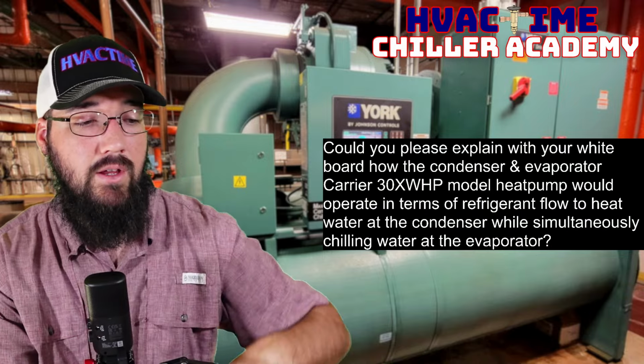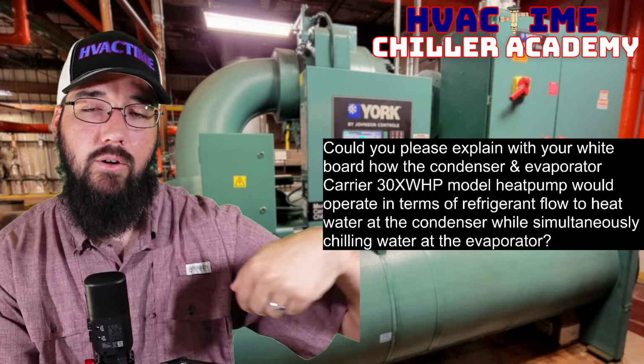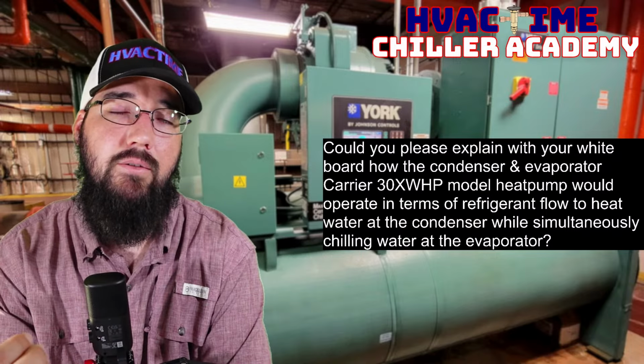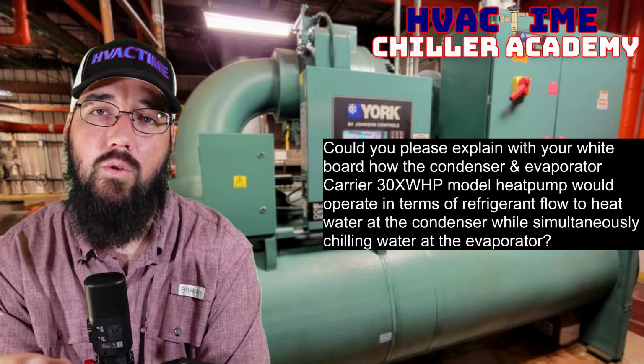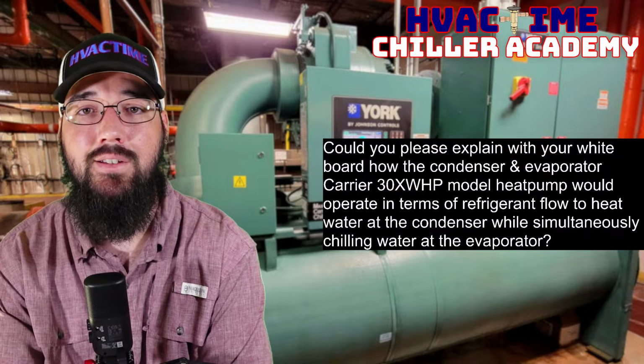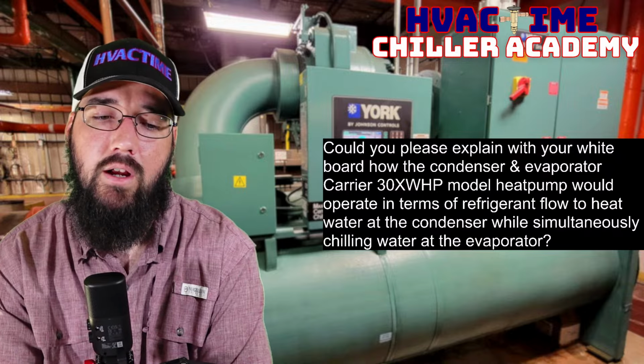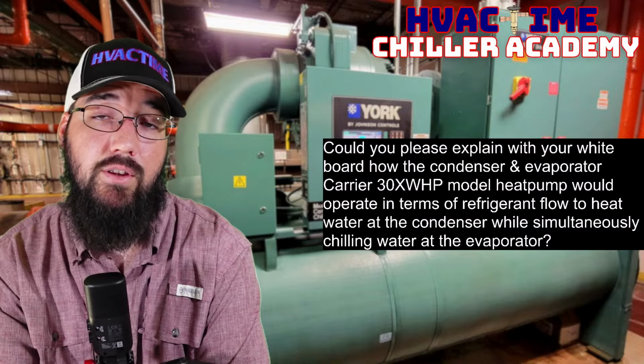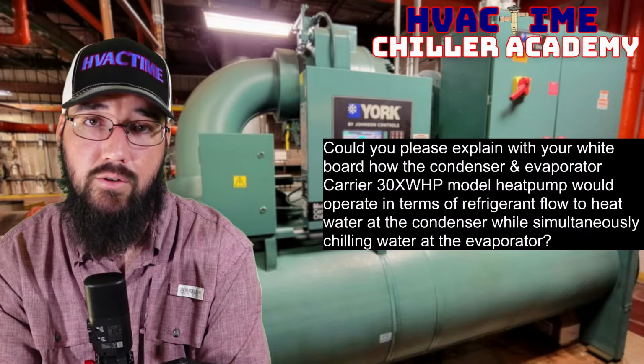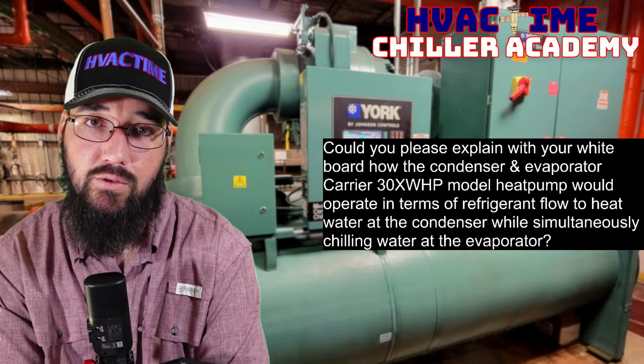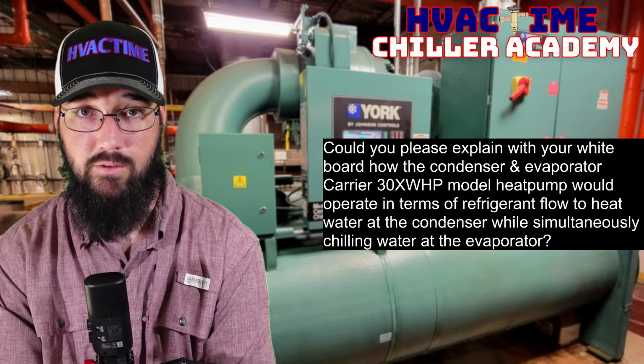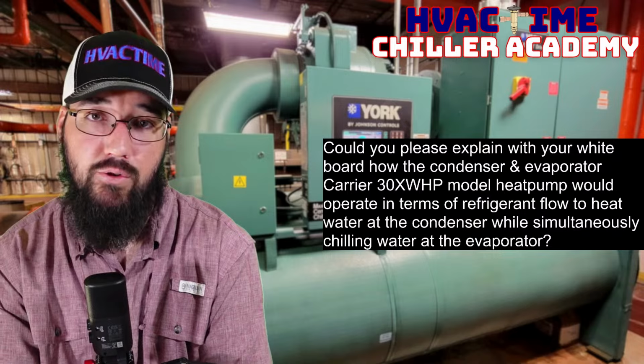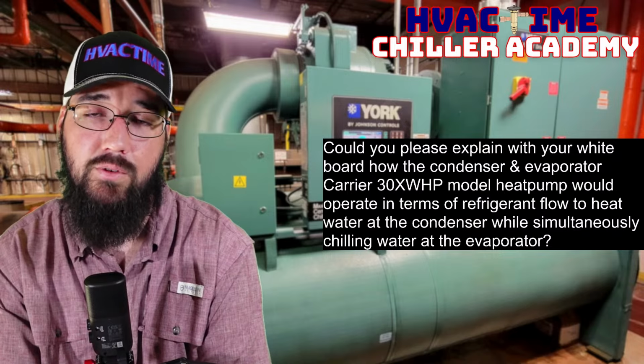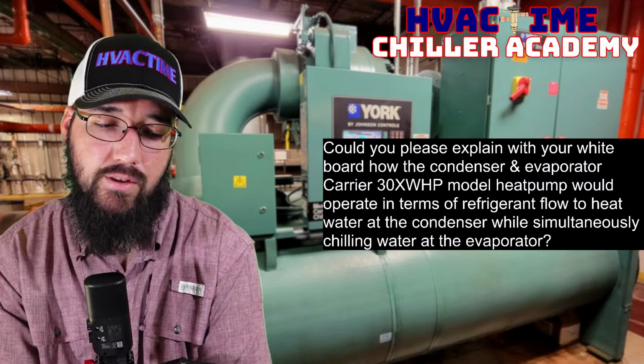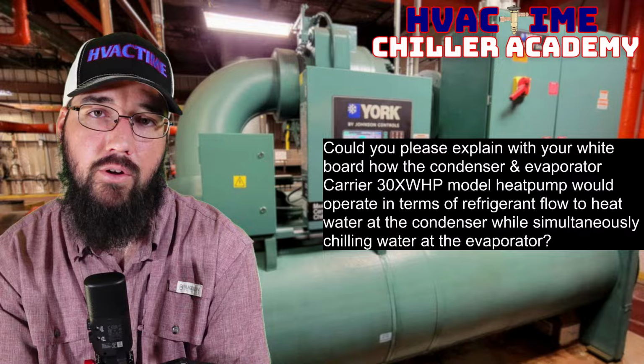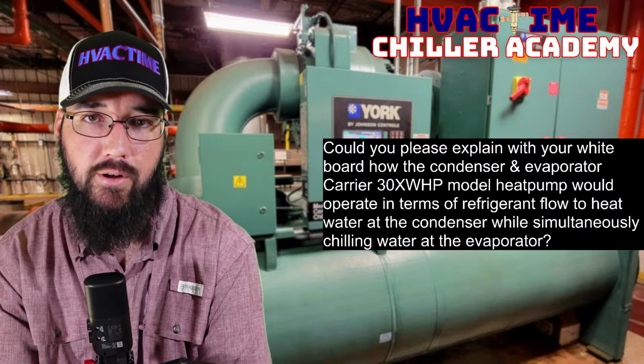And in that process, we reduce the load and we allow the primary cooling system to unload some, because it's not having to process the entire load on its own. And that's one reason why it's recommended that they configure these to run chill water on the evaporator and not try to pipe in through the condenser water, because one, a lot of these systems run open loop condenser. So that's a lot of trash that you could potentially be pulling into the chiller trying to run on the open loop side of the condenser. In addition to that, at that point, you're taking some load off of the cooling tower, but you're not taking any load off of the primary cooling system.